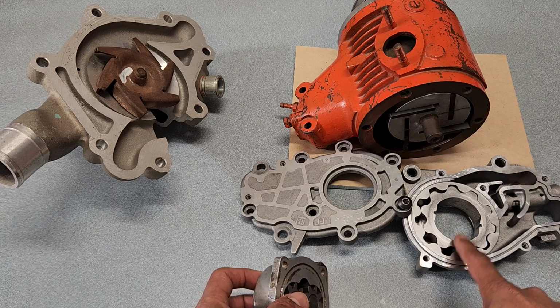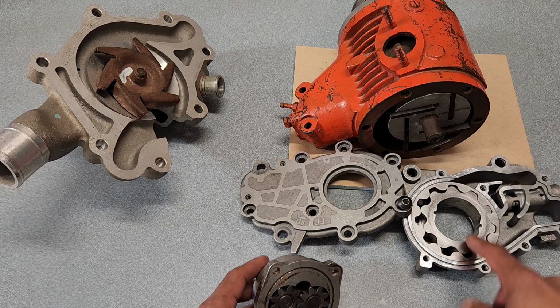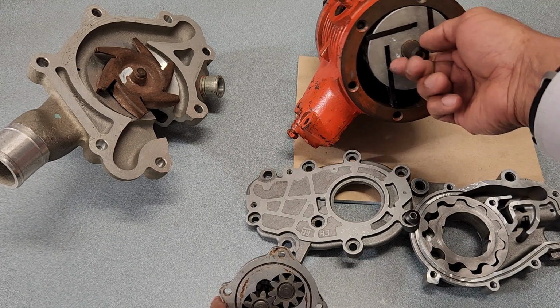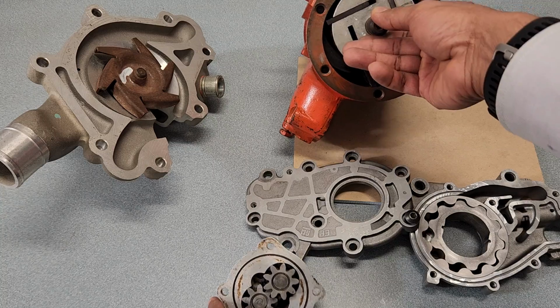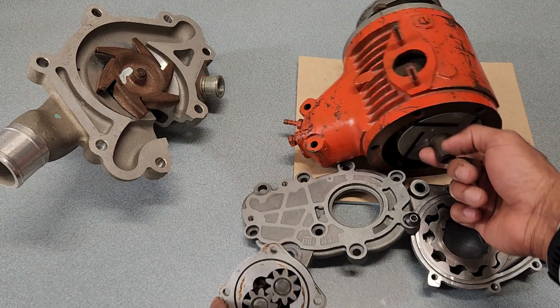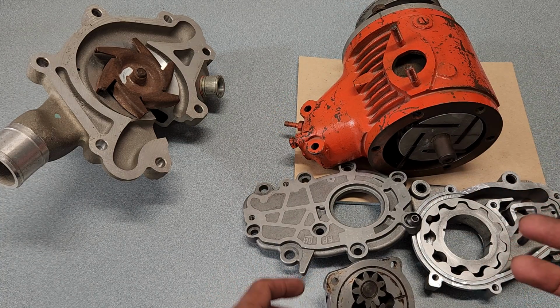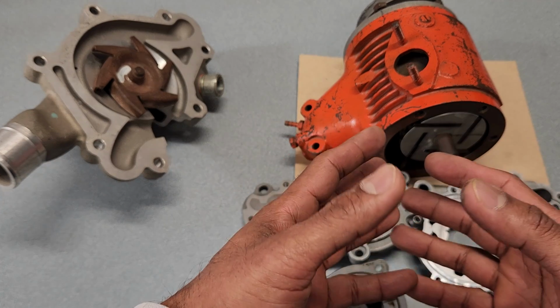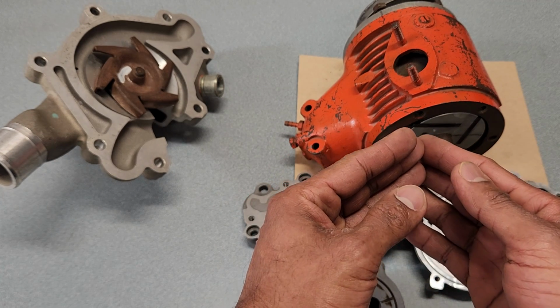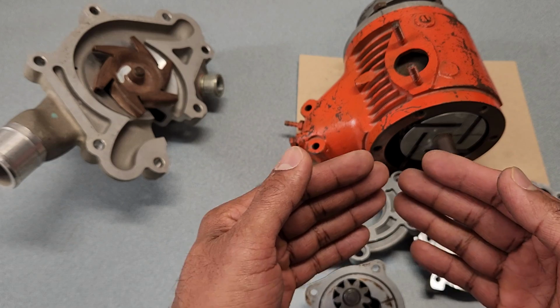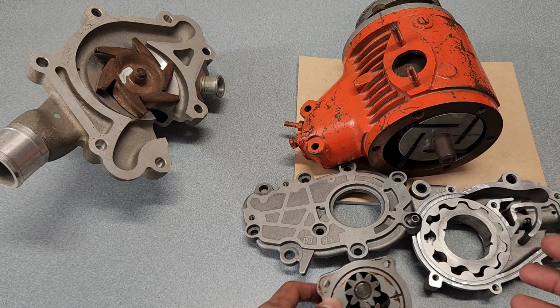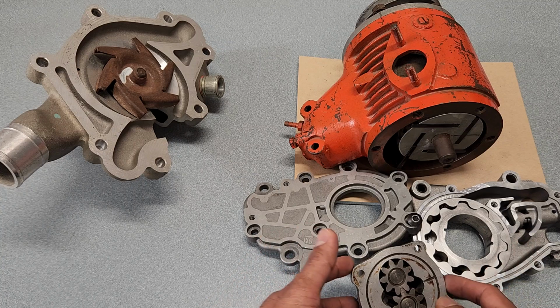This oil pump, the lobe type, also does the same thing. This vane compressor can also be called a pump if it's handling liquid. They all squeeze the flow and force it into a smaller volume, and because of the restriction it cannot go anywhere, so the pressure starts to build up. So that's why it's called the positive displacement pump.